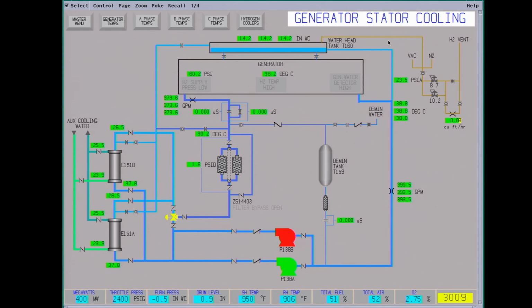There is a hydrogen vent here. You do monitor for hydrogen. The pressure here is lower than inside the generator. So if there is a tube leak or a leak on any of the tubing, the hydrogen will flow into the system, and then it will be vented over here. So you can measure leakage. So if there is a leak, the water will not go into the generator, but the hydrogen will come out into the water system so you can vent it. This unit is critical to run.